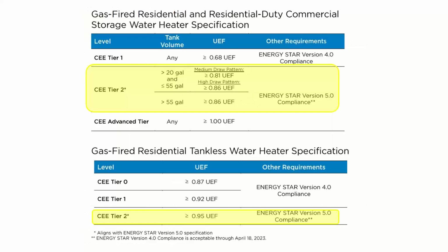Here's the efficiencies you have to hit—once again, the highest non-advanced tier. Most people have 40 or 50 gallon water heaters, so you need a 0.81 uniform energy factor, basically an 81% efficient water heater. If you have bigger units, there are different efficiency ratings you have to hit.